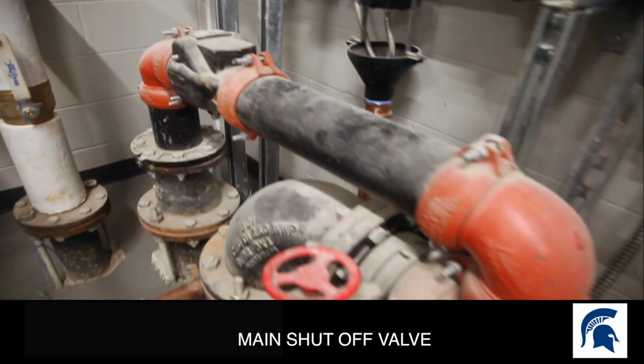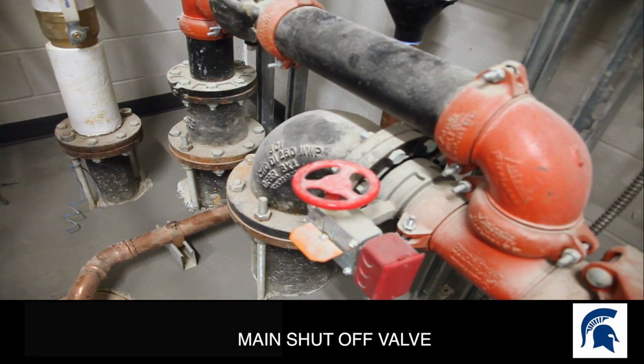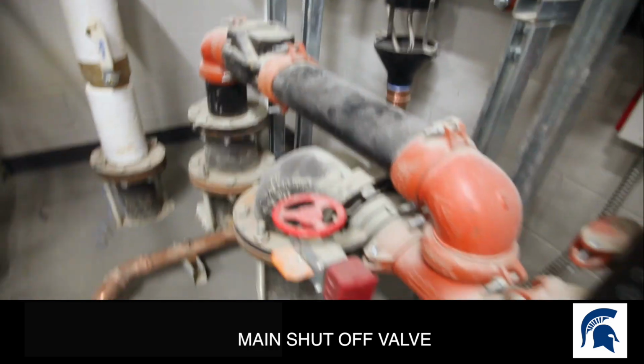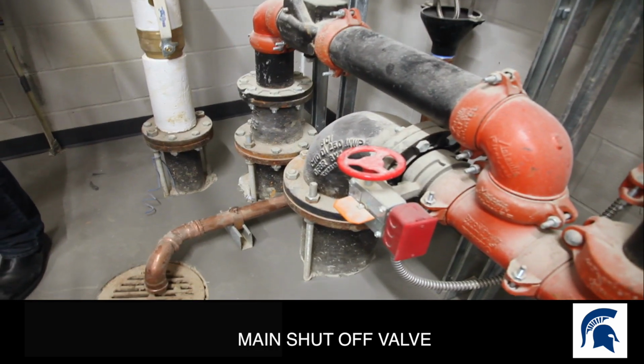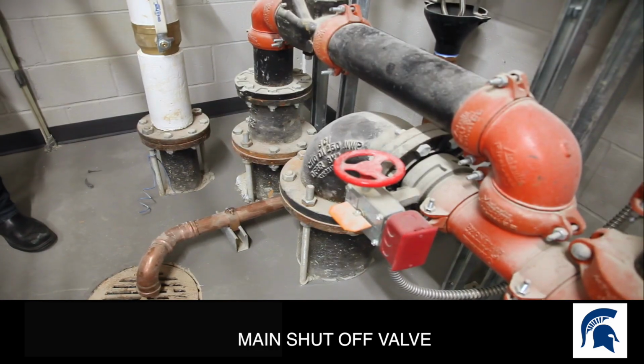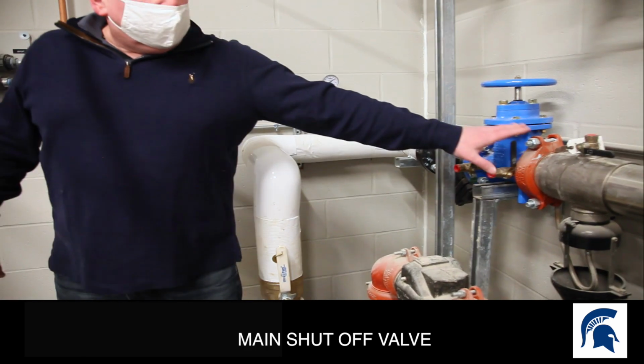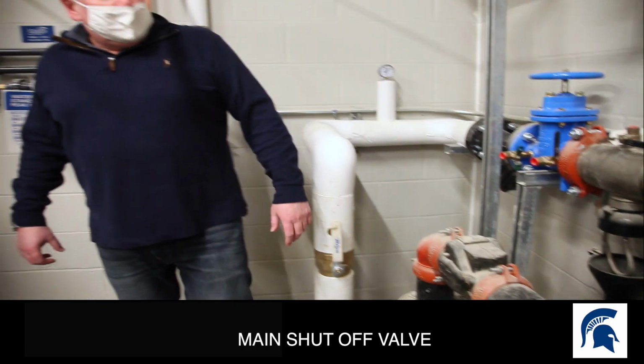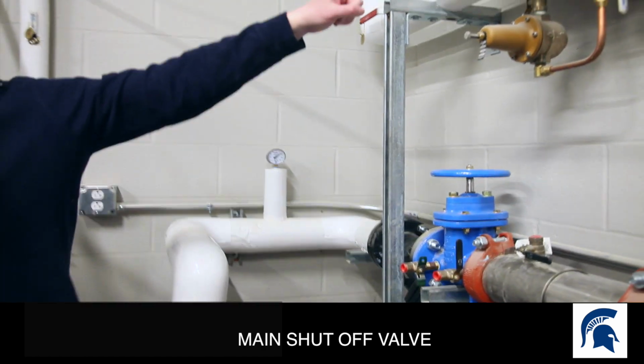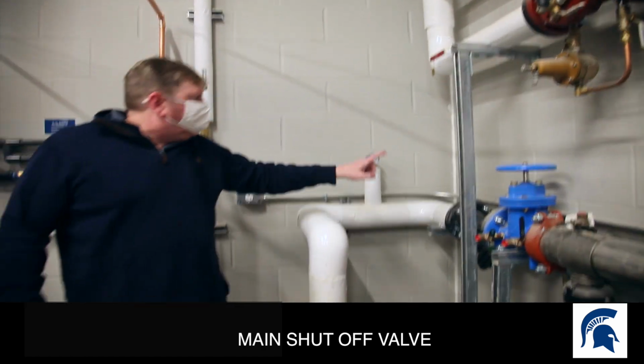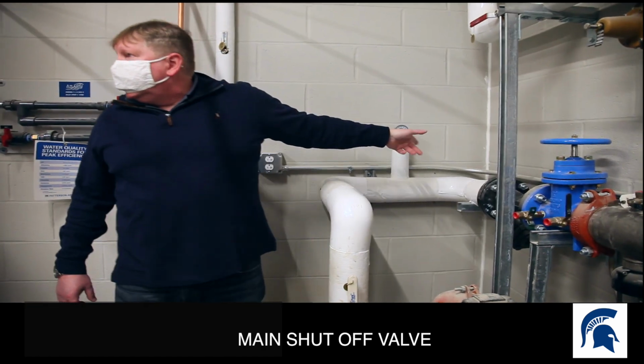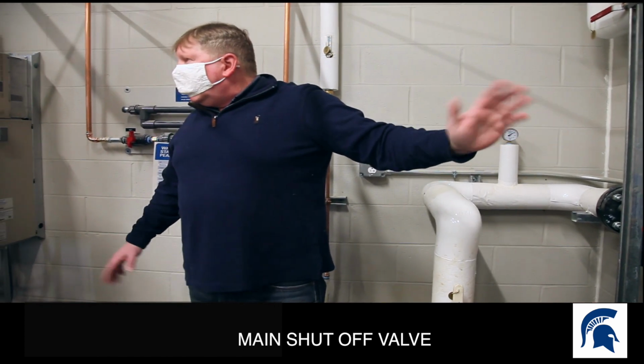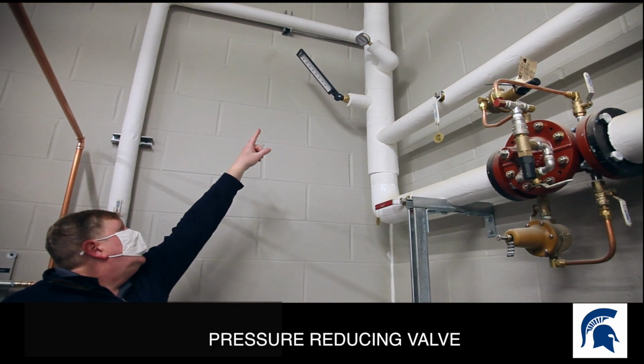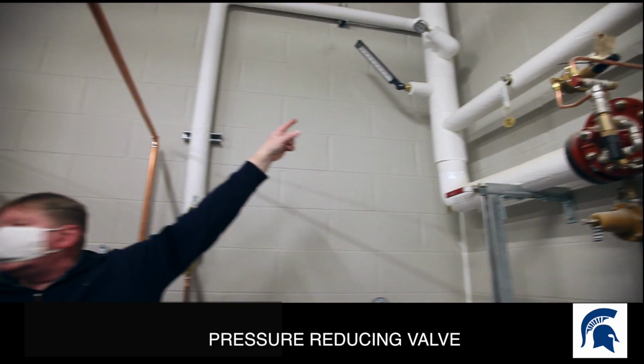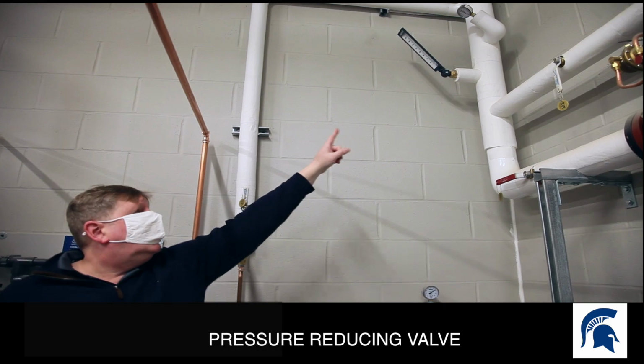There's no separate feed from the library. So the library water comes from here. Does the hot water from here feed the library also? Yes, it does. And they had to put meters on so that you could bill them or whatever. A pressure reducing valve, because you have 120 psi coming into the building. You can't run your flush valve like that, it's too hard. So this is reduced down to like 80. There's a pressure gauge up there.